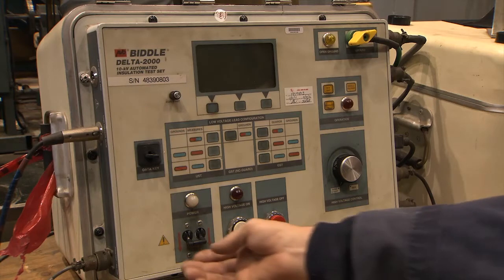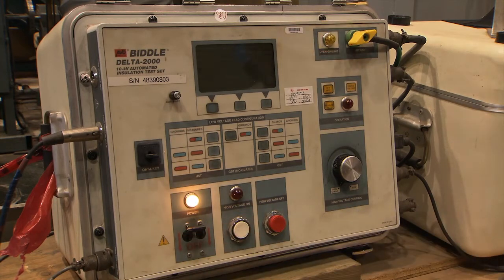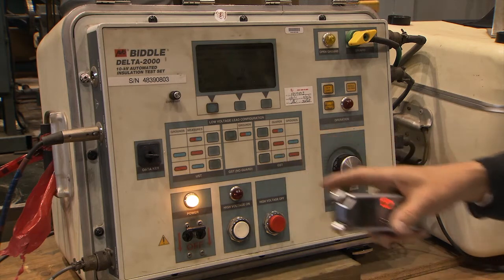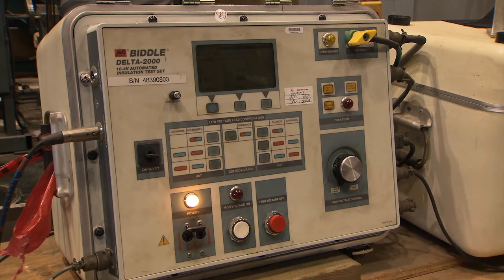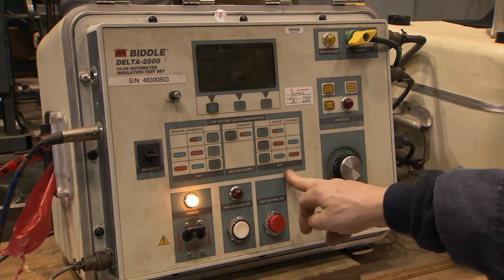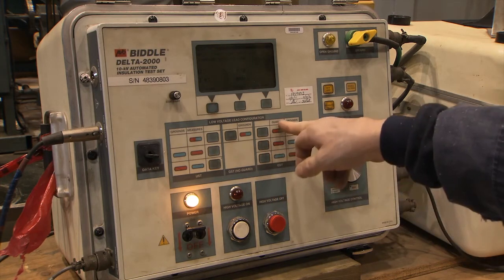Manually turn the power switch to on, and the white power switch light goes on. The yellow open ground light next to the ground terminal goes on briefly and then goes off. Press the GST test mode button for guards red and grounds blue option on the low voltage lead configuration panel.